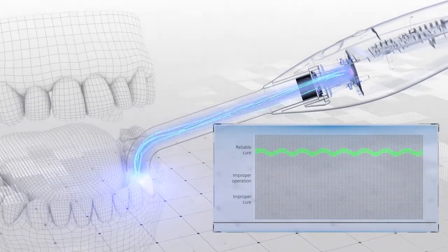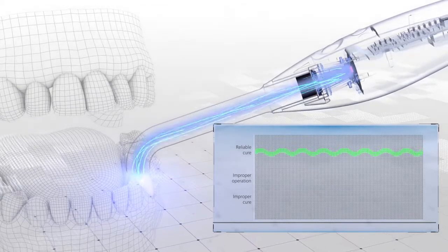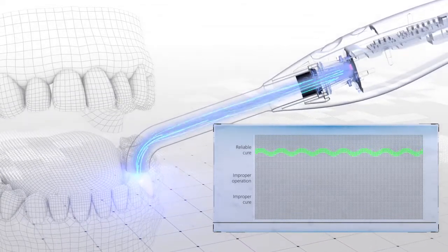The sensors of the BluePhase PowerCure will measure the reflection of the emitted light. This helps the device to automatically recognize whether the light guide is directed towards a reflecting surface, such as a composite material or a tooth.